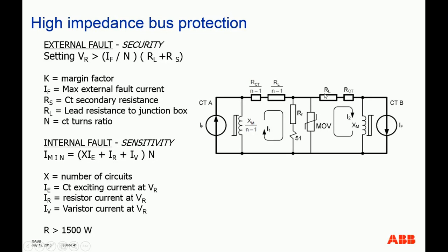So the current through this branch will create a voltage drop across these two resistors. These are the CT lead resistance and also the CT winding resistance. For the completely saturated CT, this is basically a short circuit. So really this branch will feel the voltage of this current flowing through RL and RCT, the two resistors. That's why, to calculate the operating setting, this type of relay really becomes a voltage relay, an overvoltage relay.